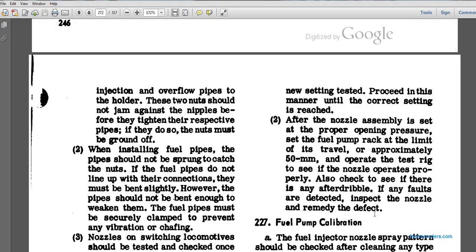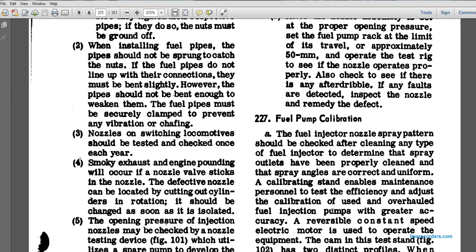After the nozzle assembly is set and the proper opening pressure set up, set the fuel pump rack at the limit of its travel, approximately 50 millimeters, operating the test rig to see if the nozzle operates properly. Also check to see if there is any after dribble. If any of these faults are detected, inspect the nozzle and remedy the defect.